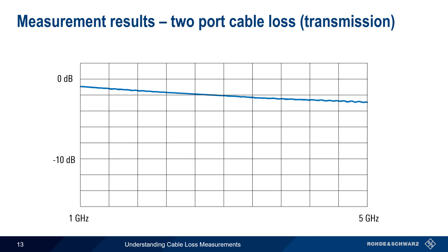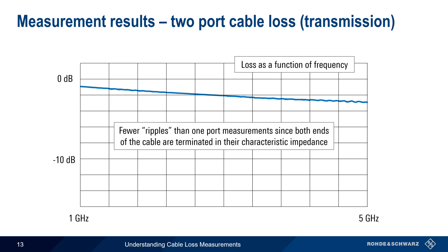Let's look at a two-port or transmission cable loss measurement using the same cable and settings that we used for the one-port measurement. We see that loss is still a function of frequency, but notice the trace has fewer ripples than the one-port measurement. This is because the cable is terminated in its characteristic impedance on both ends. Although there are many cases where attaching both ends of a cable to a VNA is not practical, two-port cable loss measurements are generally preferred over one-port cable loss measurements whenever possible.